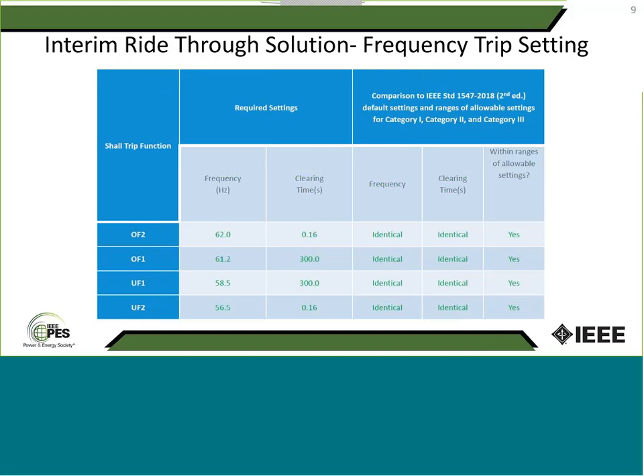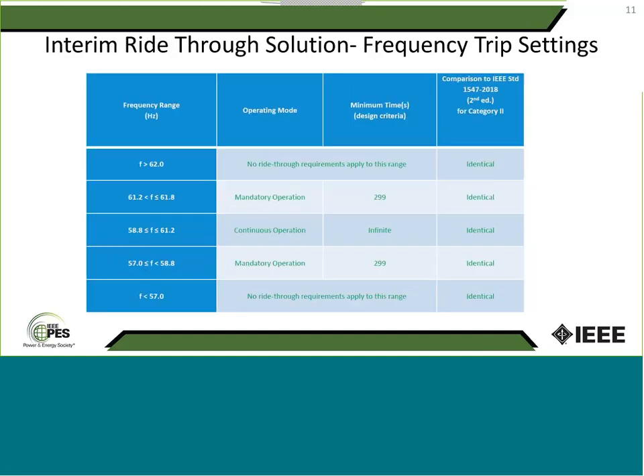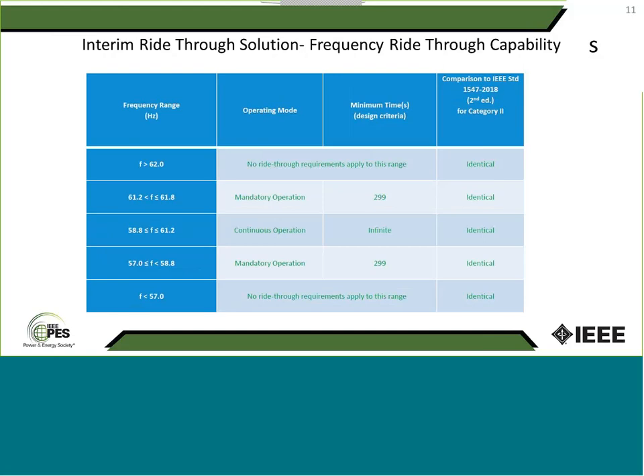With regards to frequency ride-through, these are the frequency trip settings. Based on the experience we had in Mass, we've been complying with the NPCC Directory 12 under frequency load shed curve anyway. So adopting these trip settings really was not a big challenge or big deal for local utilities in the state. We are already compliant with these settings, so it was not a big deal for us to adopt the ISO New England's requirements. Again, there are 2 over frequency set points and 2 under frequency set points. You see the settings on the slide.